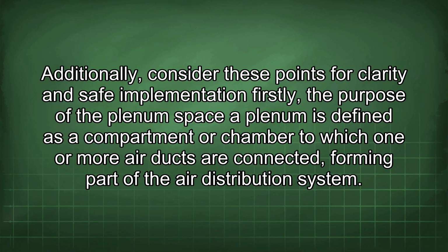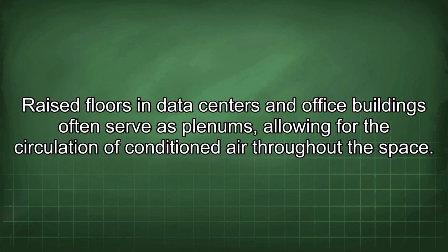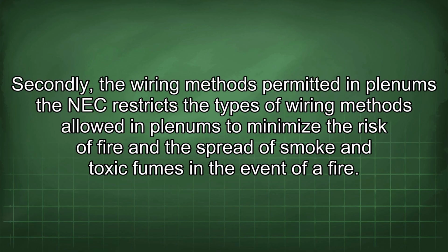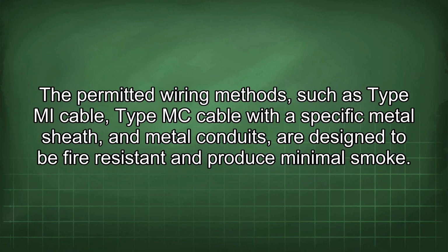Firstly, the purpose of the plenum space. A plenum is defined as a compartment or chamber to which one or more air ducts are connected, forming part of the air distribution system. Raised floors in data centers and office buildings often serve as plenums, allowing for the circulation of conditioned air throughout the space. Secondly, the wiring methods permitted in plenums. The NEC restricts the types of wiring methods allowed in plenums to minimize the risk of fire and the spread of smoke and toxic fumes in the event of a fire. The permitted wiring methods, such as type MI cable, type MC cable with a specific metal sheath, and metal conduits, are designed to be fire resistant and produce minimal smoke.